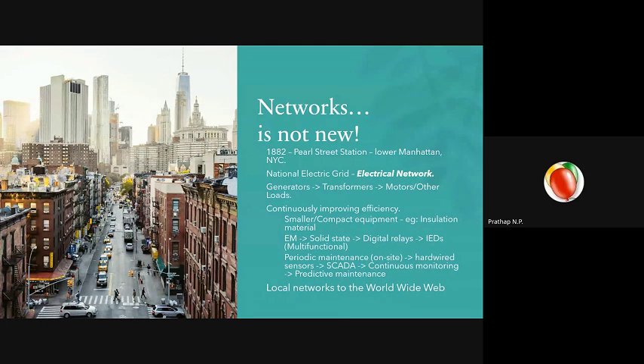The same way breakers were so huge in the early 1900s, but now breakers are small. Although they need clearances in high voltage situations, the operating mechanisms have come down in size. Similarly, CTs - CTs were one of the untouched parts in the power system, CTs and PTs both. They were huge, they had to be wound, and you cannot open circuit a CT - it's dangerous. But now with advancement in technology, we have optical CTs.